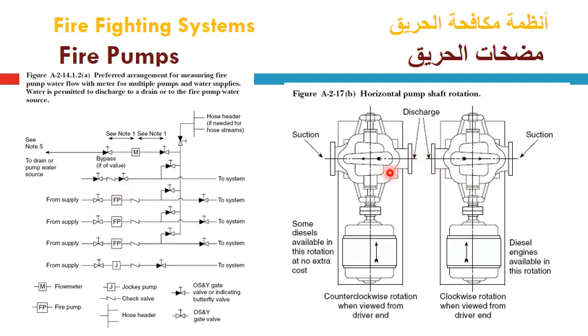On this figure on the right hand side we can see the difference between the rotational directions of the shaft, either counterclockwise rotation when viewed from the driver end, or clockwise direction as shown by both arrows, in clockwise rotation when viewed from the driver end, for both available diesel engine rotation and for electrical motor. The suction flange and discharge flange will be switched according to this rotational motion, either counterclockwise or clockwise.